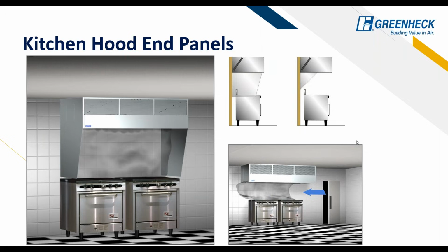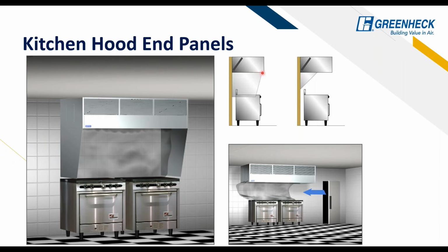Okay, so speaking of the vertical end panels that I mentioned with solid fuel, we have two different options. We have full vertical end panels, and I apologize, this picture is a little bit out of date here. These actually go all the way down to the ground, and they basically enclose the hood and really increase the capture and containment rate, as well as reduce the clearance or the overhang options. So you can go down to technically 0-inch overhang with full vertical end panels.